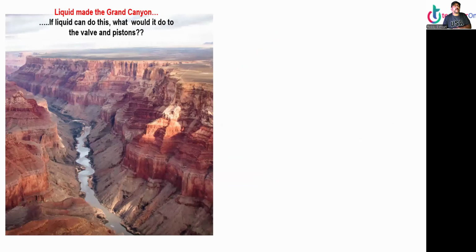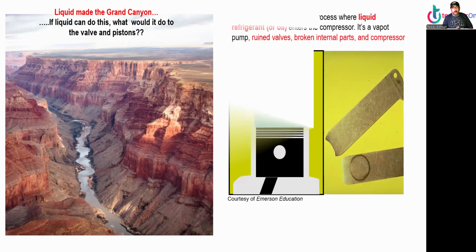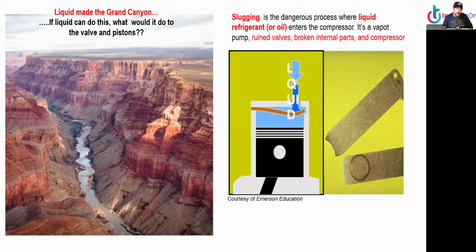Now, compressor slugging. Let's talk about slugging. Liquid made the Grand Canyon. If liquid can do this, what do you think is going to happen to my piston and my valves? Slugging is a dangerous process where liquid, refrigerant, or oil enters the compressor. It's a vapor pump. Vapor pump, misspelled. Liquid ruins the valves, breaks internal parts, and ruins compression. We cannot compress liquid, very important. I don't care if it's titanium alloy. You cannot compress liquid.